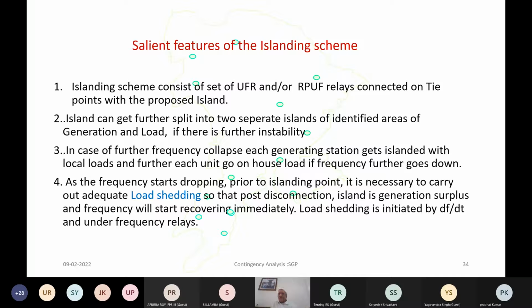So there will be under frequency and dF by dt load shedding schemes to keep the power balance between the available generation and the load which is connected. And if this balance results in further sinking of frequency, then you can split the island further. So maybe North and South Delhi, or West Delhi and some of the areas, depending on the configuration of the network, you can further split. One of the key features for deciding any sub-area would again be the availability of generation in that area and the balancing of the load with that available generation. So again, generation and load balancing will have to be done by load shedding and generation shedding, etc. Those schemes will have to be configured.